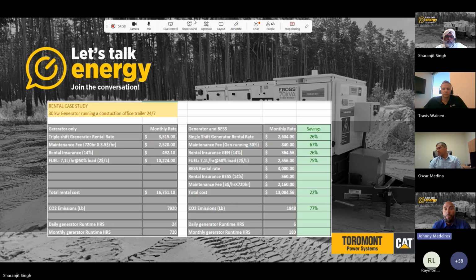If you run the generator on the left-hand side, you'd see triple shift, because it's running even with barely any load at night, but running 24 hours a day. That's 720 hours of running time during the month. Our rental rate for that 30 kilowatt generator running triple shift compares to running the generator only a single shift, where the rental rate would be less. So right off the bat, the customer would save about 26% on the rental rate.